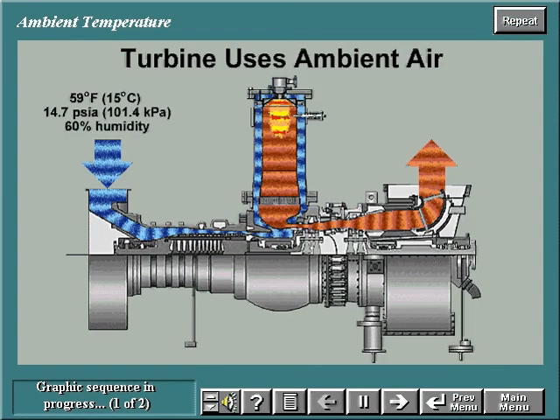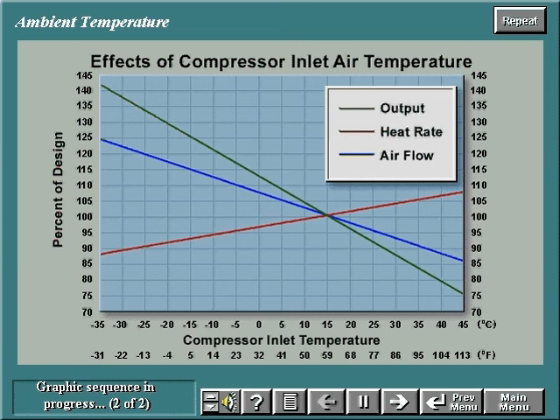The gas turbine is an ambient air-breathing machine. Therefore, its performance will be changed by anything affecting the mass flow of the inlet air to the compressor, such as changes in temperature, barometric pressure, and humidity. The temperature of the air entering the compressor inlet affects output, heat rate, and air flow. These effects are illustrated in this graph.